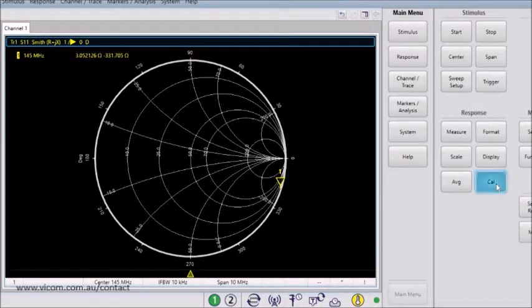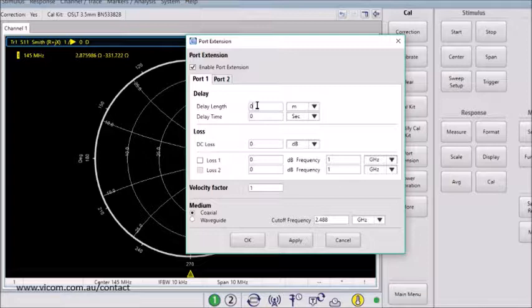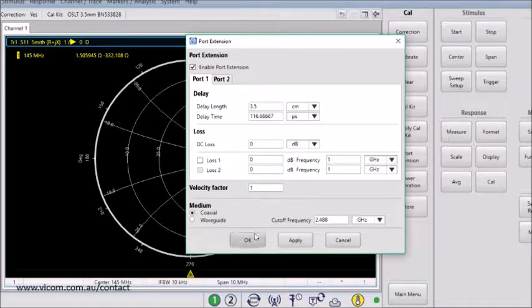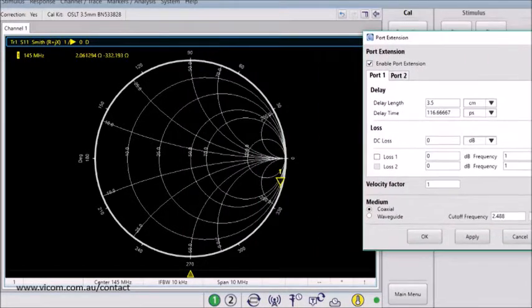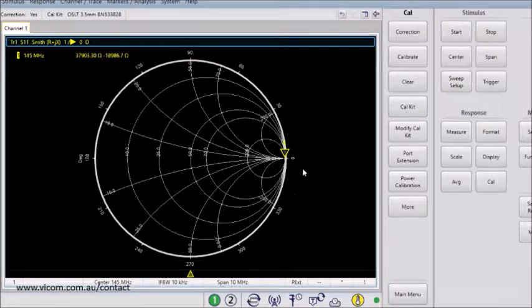So, I'll go to Cal, Port Extension, Enable. Let's try three and a half centimeters. And click Apply. Let's see where this puts us. Almost there. Let's try a little bit more. All right. And there we go. So, now we've properly moved our calibration plane so it's aligned with where we're going to place the matching network.